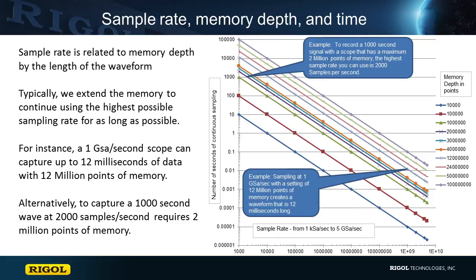The chart to the right shows a line color for different memory depth values from 10,000 points to 100,000,000 points. Along the x-axis is the sample rate settings from 1 kS per second up to 5 gigasamples per second. The y-axis shows how long in time can be continuously captured with the memory depth and sample rate settings. Note that these are all log scale axes.